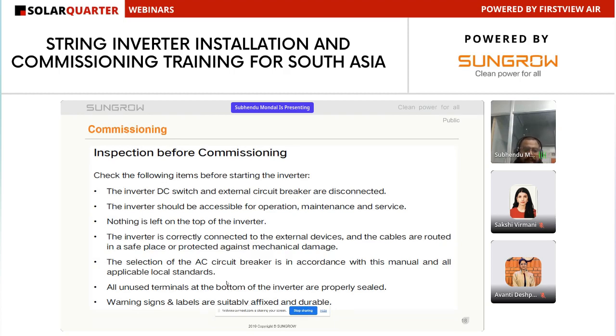Then the cable selection of the AC circuit breaker should be according to the manual and the local standard. All unused terminals and the bottom of the inverter are properly sealed. Sometimes what happens is, when we are doing termination of the AC cable, there are some holes. Maybe some external things go inside and will damage our inverter. So we have to close all the holes and all the terminal holes. And warning signs and labels should be flexible and durable.